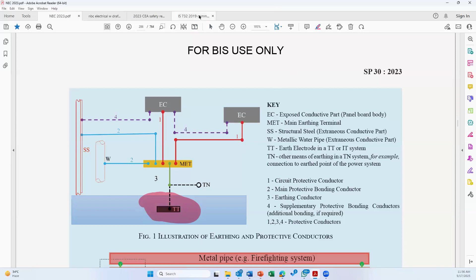Now you are relying upon an earth electrode only in the case of a TT system here. If you don't have a TT system, you don't need to have an earth electrode. For example, IS 732, which is the code of practice for wiring. I am taking you to a clause which is 5.5, 5.4.